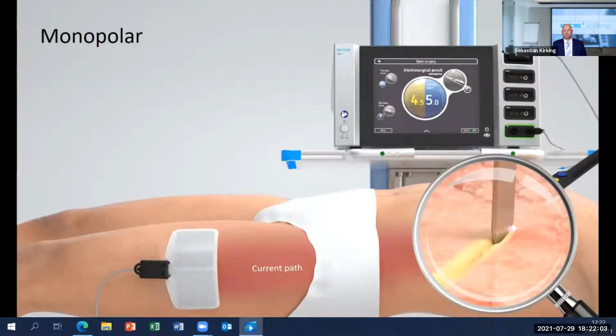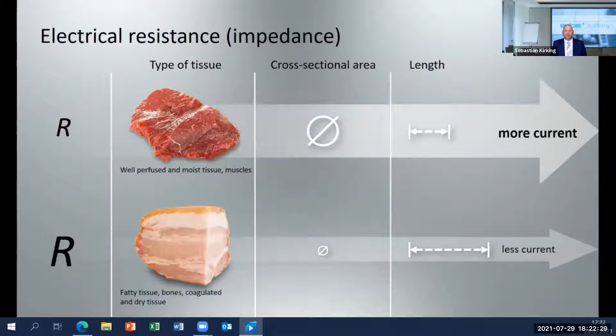As you see, the current flows through the patient, but the electric path is not necessarily straight as the current follows the path of least resistance. The resistance depends on the type of tissue. Fatty tissue and dry coagulated tissue have higher resistance than blood and muscle tissue, for example. Also, the diameter and the length of the current path have an impact on the resistance. Therefore, the current will mostly flow across the conditions shown above on this graph and less across the conditions shown below, where low conductivity, small diameter, and a longer path make it more difficult for the current to flow.